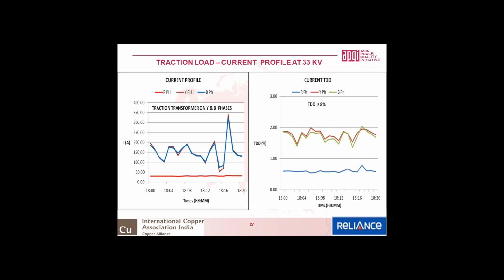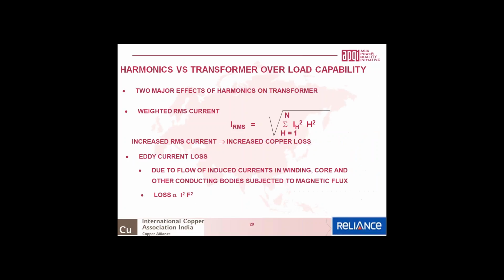A very exciting topic is harmonics versus transformer overload capability. Whenever a transformer feeds harmonic loads, there are two major effects on the transformer: increased copper loss and increased eddy current loss. Copper loss increases because the RMS current itself increases, as it contains not only the fundamental but also harmonic components of the current. The eddy current loss also increases because of the increase in frequency, since eddy current loss is proportional to f squared.